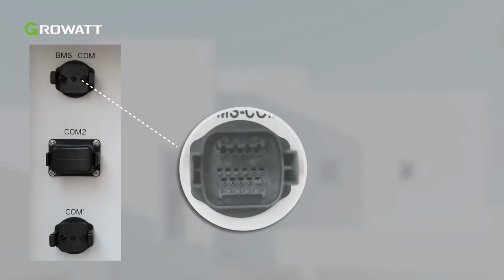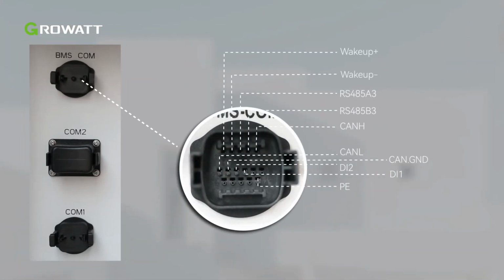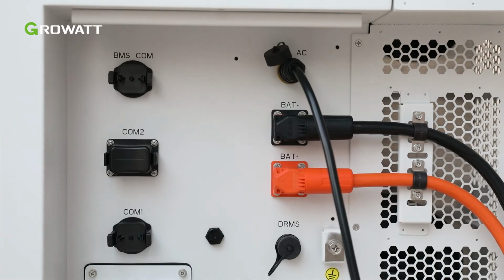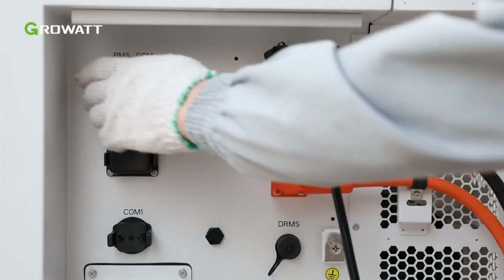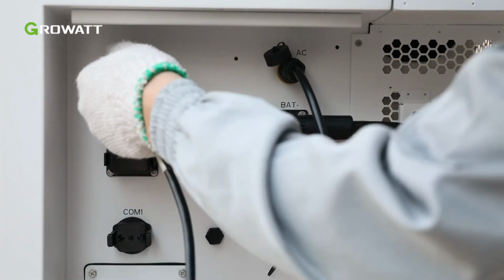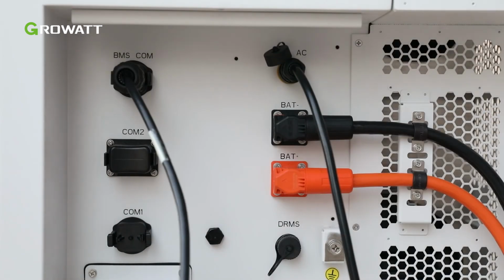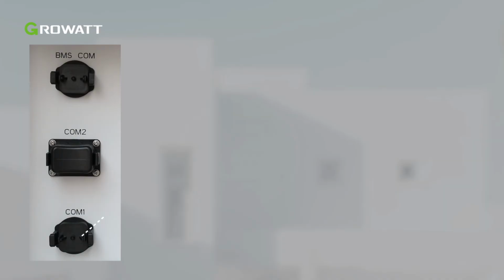The pin definitions of BMS COM port are as illustrated. Connect the communication cables to the corresponding terminals as required. Remove the dust-proof cover from the BMS COM terminal. Insert the 16-pin terminal, the client side, to the corresponding position and ensure that it is tightly connected.